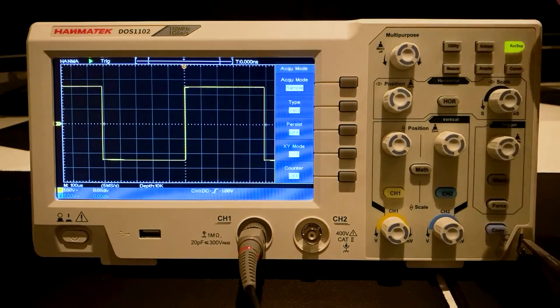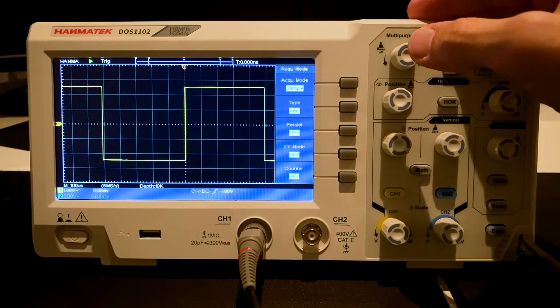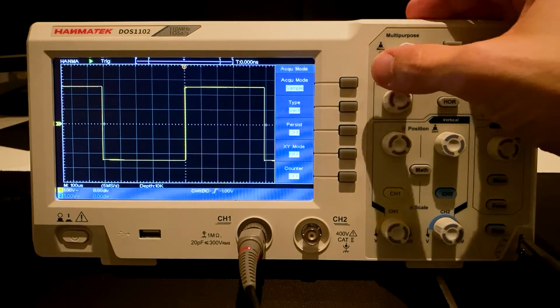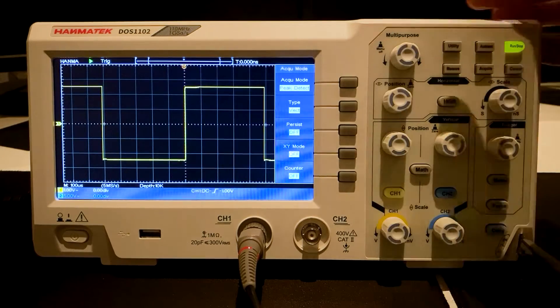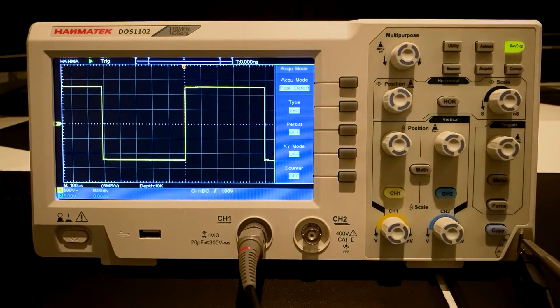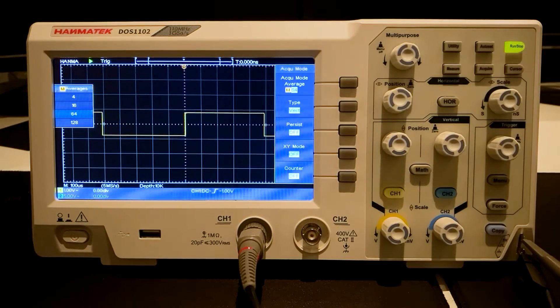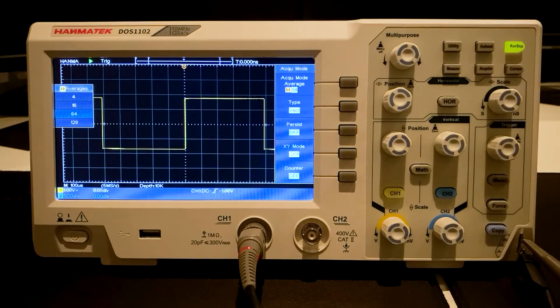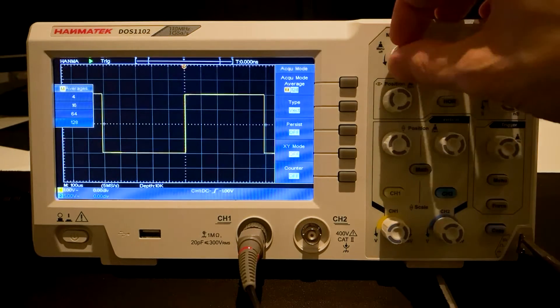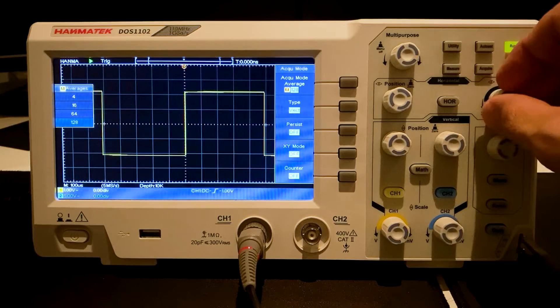The Acquire function. The Sample mode is standard and displays evenly spaced data points. The Peak Detect mode emphasizes outlying data points. The Average mode shows each point averaged over the last n captures.